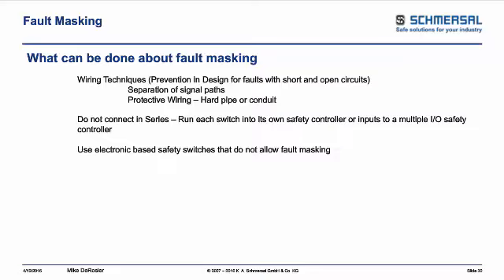But the spindle is not allowed to run because of the hazards associated with the spindle, but they can do setup, which they may have to be up close and personal and do some indexing and jogging to get the piece set up right, then close the door, come out of that mode. So sometimes it's mislabeled. I've seen cases where it was requested by the customer. The customer requested that switch to put in there, so the OEM did what was requested of them.